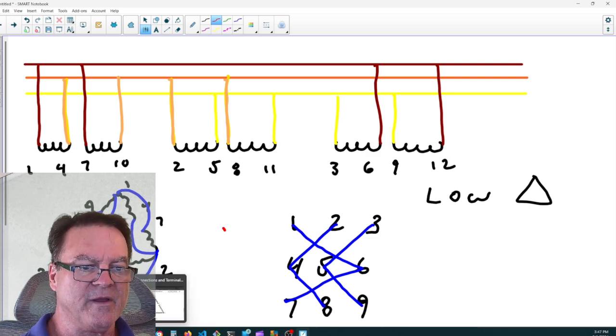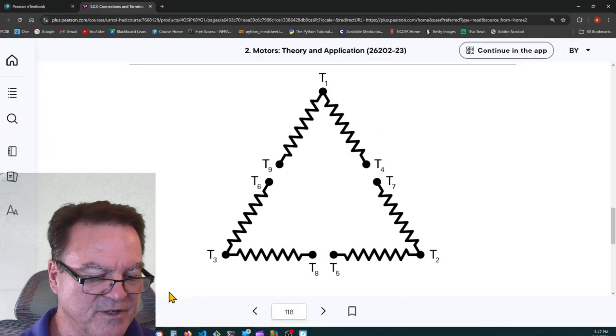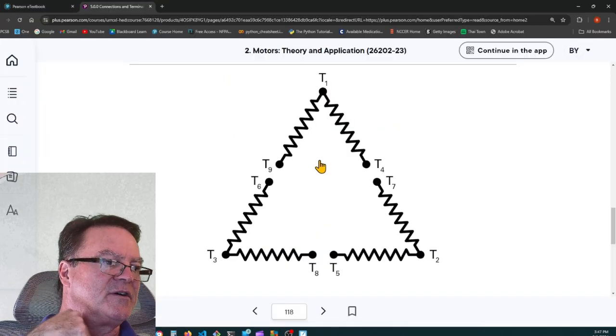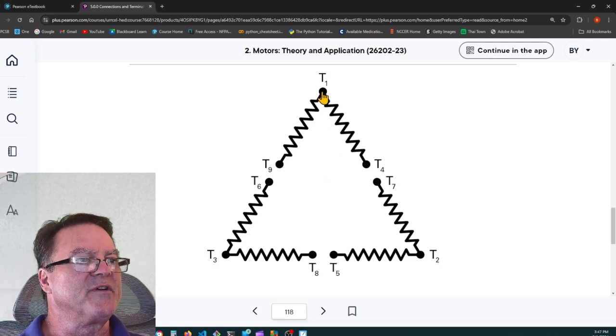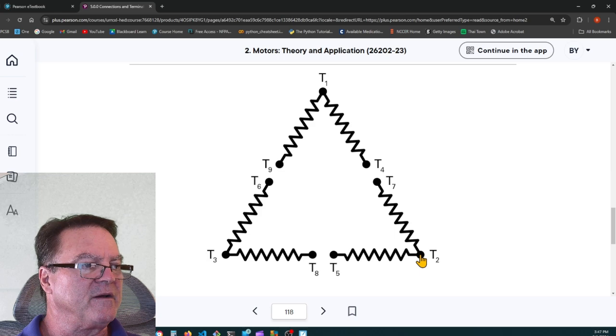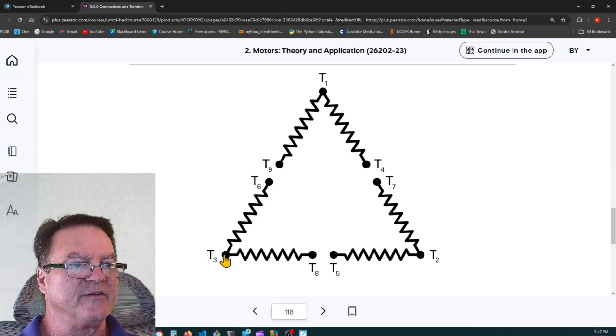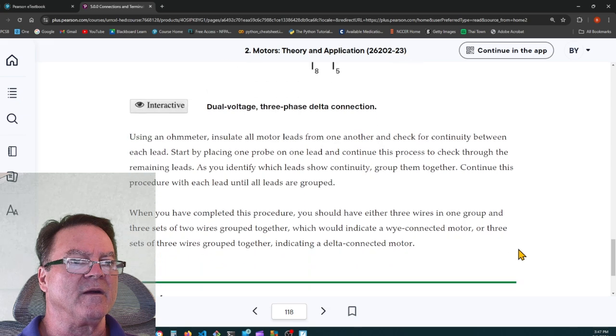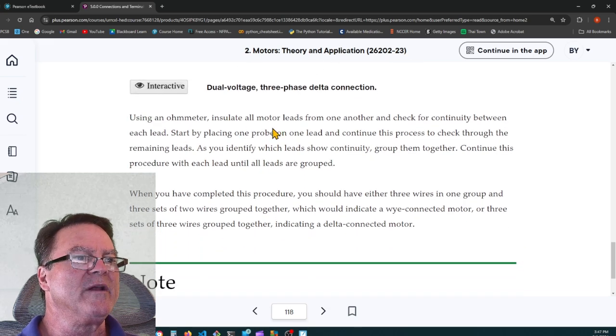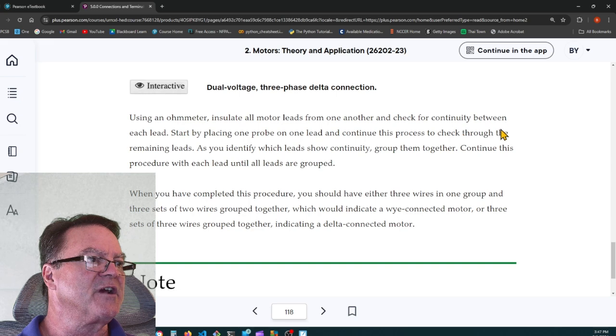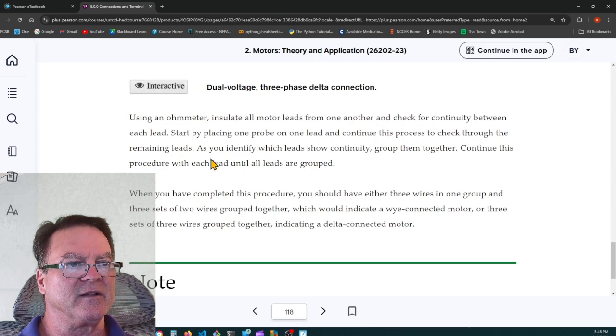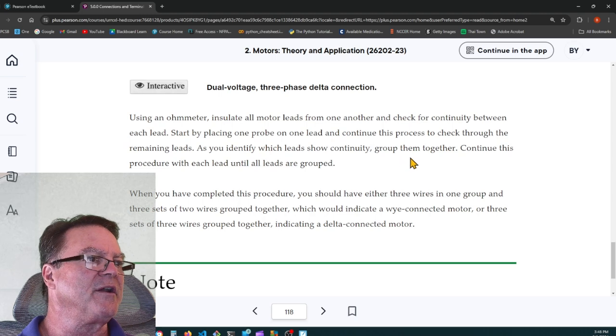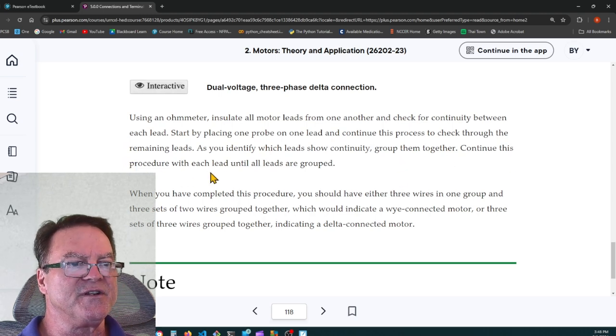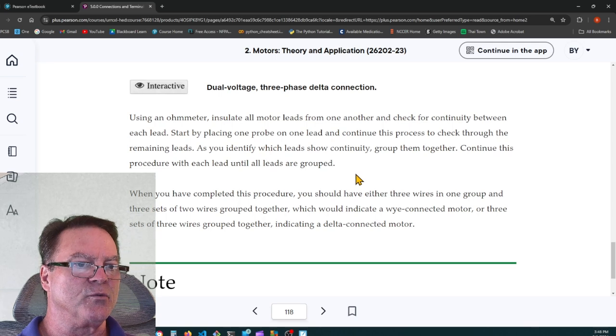But let's go back to the book, because they were telling us about delta and Y. So here are your 9 leads for delta. Again, it's 12 leads, but 3 of them are hidden. 10 and 2, 11 and 3, and 12 and 1. All right. Using an ohm meter, insulate all motor leads from one another and check for continuity between each lead. Start by placing one probe on one lead and continue this process to check through the remaining leads. As you identify which leads show continuity, group them together. Continue this procedure with each lead until all leads are grouped.